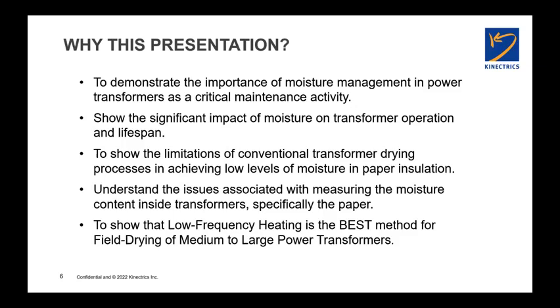So this presentation, the goals here are to demonstrate the critical nature of moisture management in power transformers in terms of protecting your asset from catastrophic failure and for optimizing its lifespan. So it's a critical maintenance activity that you need to be aware of. We want to show the significant impact that moisture has on transformer operation and its potential life, and to show the limitations of, I'll say, conventional transformer drying processes in removing moisture from the paper insulation.